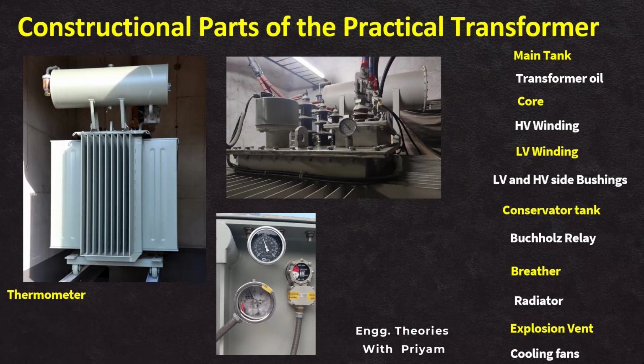The thermometer in a transformer is typically located on the transformer tank and plays a crucial role in monitoring the operating temperature of the unit. Positioned near the winding or immersed in the transformer oil, the thermometer provides essential information about temperature conditions within the transformer. This data is vital for ensuring the transformer operates within safe temperature limits, preventing overheating that could lead to insulation degradation or other faults.